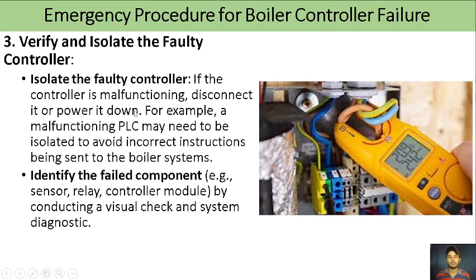Next, verify and isolate the faulty controller. If the controller is malfunctioning, disconnect it or power it down. For example, a malfunctioning PLC may need to be isolated to avoid incorrect instructions being sent to the boiler system. Identify the failed components, like sensor, relay, controller module, by conducting a visual check and system diagnostic. Usually, if the PLC is a problem, and we don't have programming onboard ship, we will have to wait for technicians to do it. But if the problem is sensors, relays, controller module, we can do something about it. Maybe we have spare parts, or we can rectify the problem.